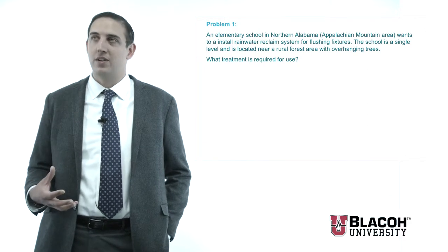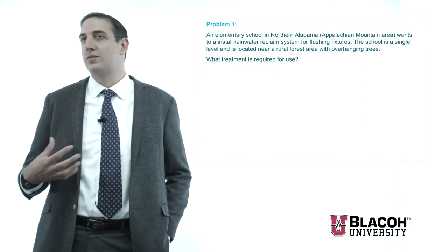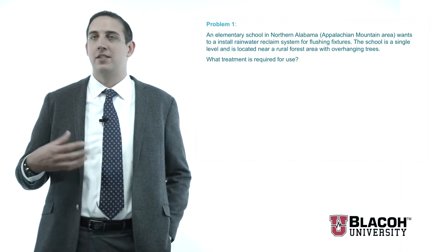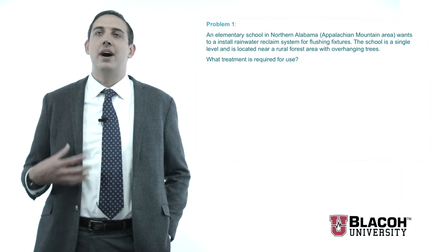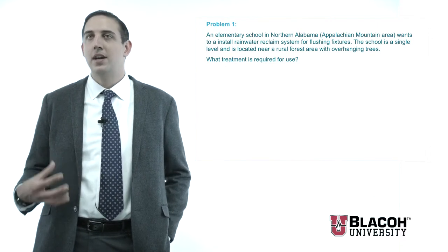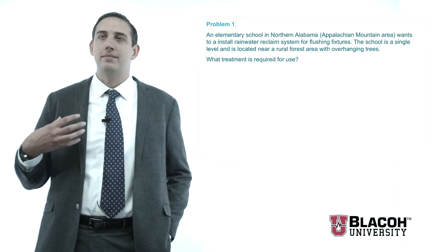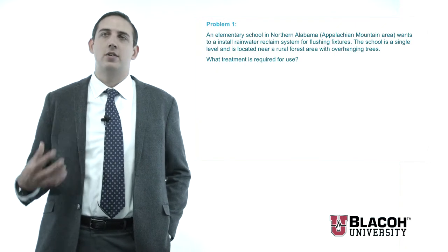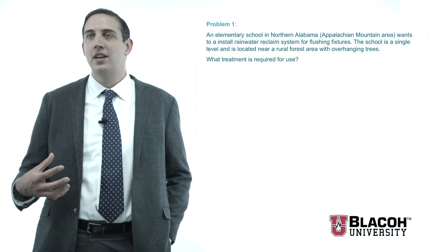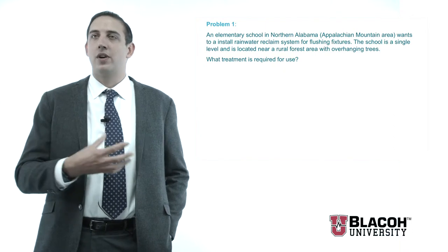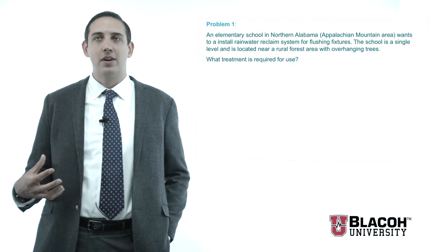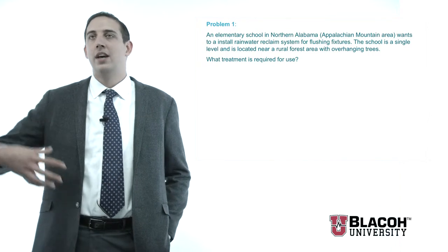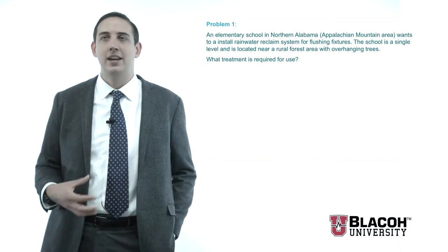We also have overhanging trees most likely, which are going to overhang onto our first-floor building. Looking at both what's around the area and the catchment surface elevation, I'm going to see a higher than average biologics buildup and a slightly higher than normal particulate buildup due to that lower elevation. As for the material of construction — being in the southeast, we don't have a lot of acid rain and probably don't have the metal leaching issues you'd typically see in a location like New York.